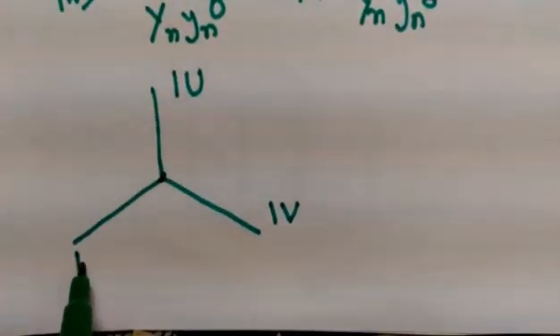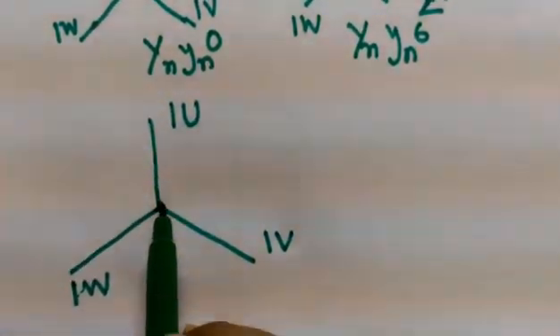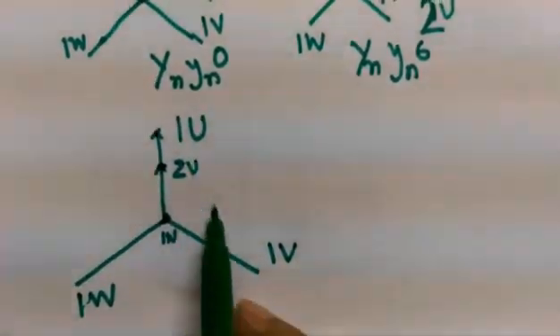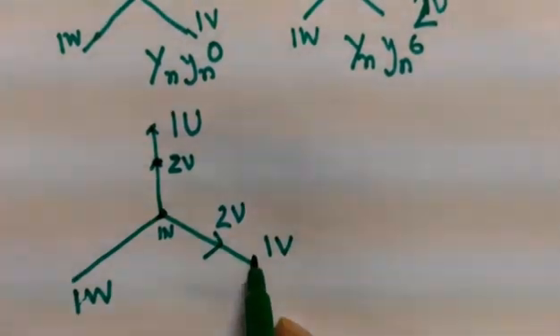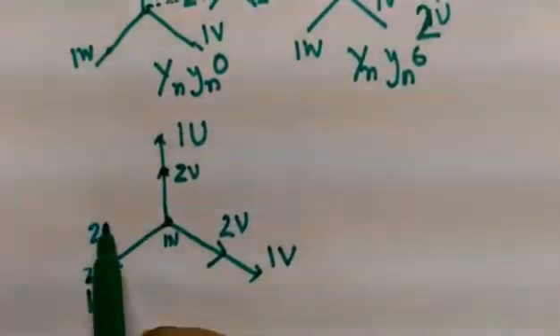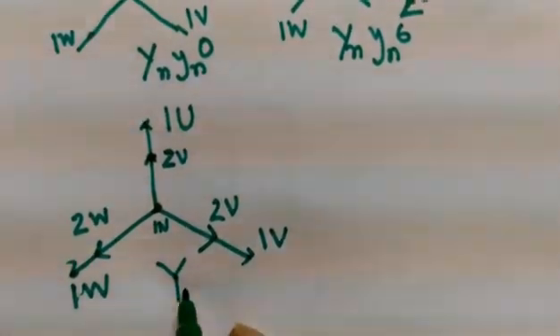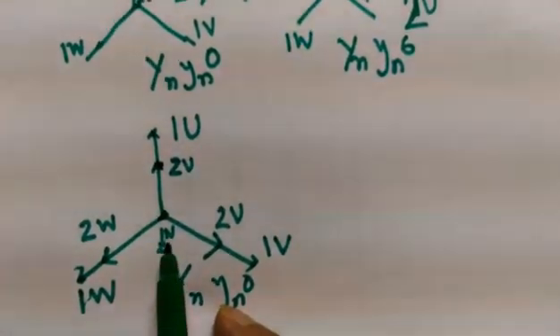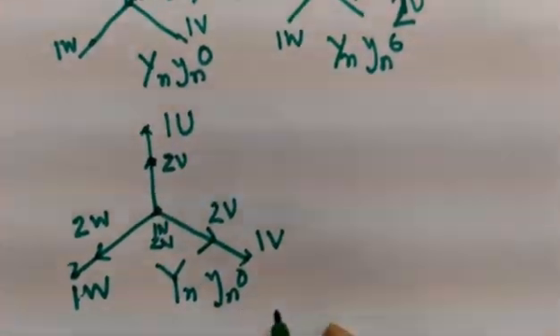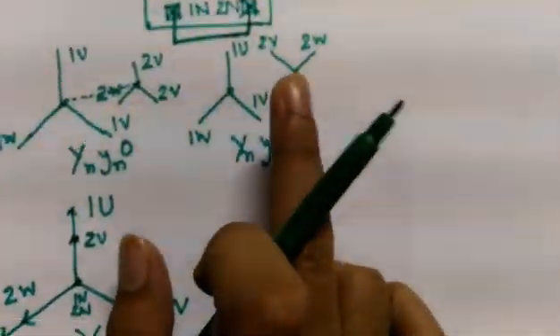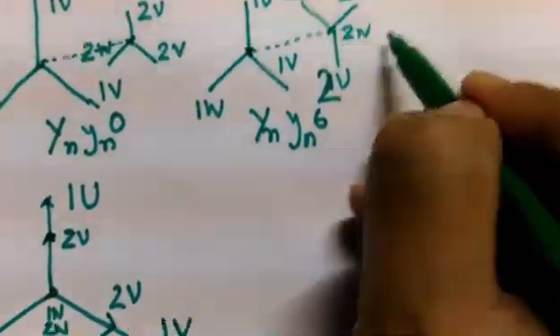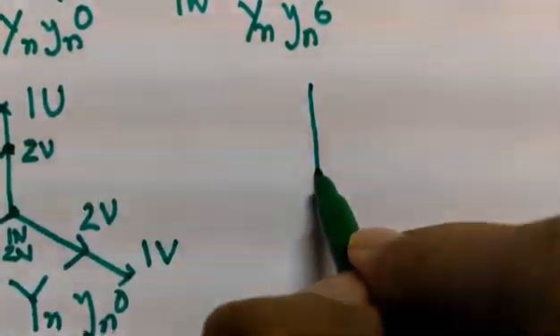If the transformer is YnYn0, this arrangement will give you a resultant phasor where 1U, 1V, 1W are on the primary side, and 2U, 2V, 2W are in the same direction — the resultant phasor will be of this form. If the vector group is YnYn6, shorting of the two neutrals will give you a resultant phasor in the opposite direction.